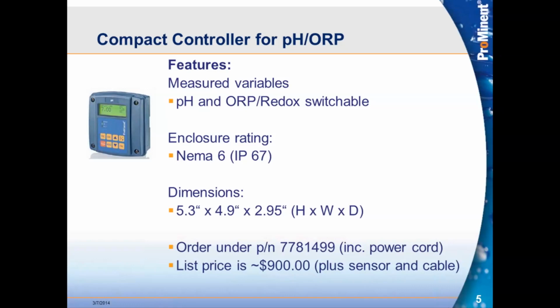The enclosure rating is NEMA 6, so it's very good, very weather tight. We would still recommend, if you're putting it outdoors, to cover the unit. LCD displays, if they're left exposed to the sun in particular, will bleach out very readily, so please be observant of that. Dimensions are very similar to the DMT. So you're just under 5.5 inches by 5 inches by about 3 inches. So it's a very small, compact unit. Go figure, being called the compact controller.